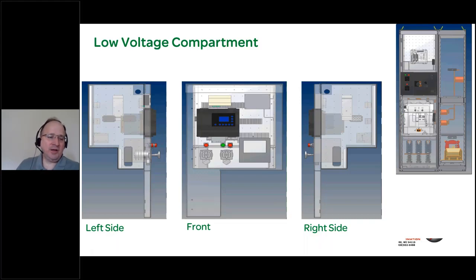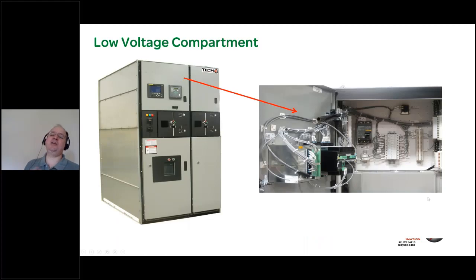The low voltage compartment, I have just some diagrams here with the left, front, and right sides of it. There's a separate compartmentalized low voltage compartment. If the arc quencher option is utilized, this is where we put our arc quencher controls as well. Again, this is not an arc quencher presentation. There's a separate L3 webinar on active arc quenching, but that option to deliver an IEEE C37.20.7 solution without mechanical venting, without plenums, is available in this equipment.